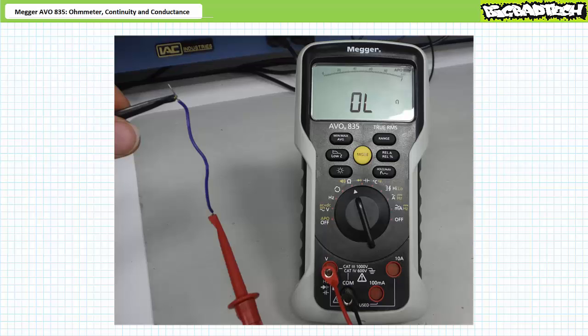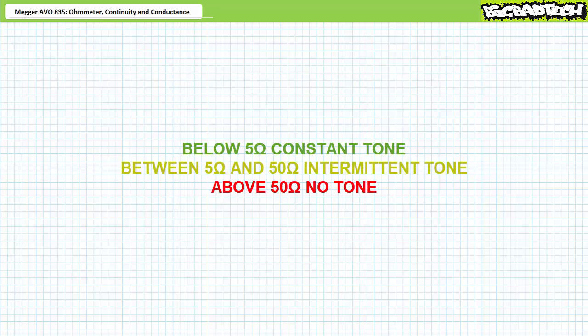Ohmmeter works for these types of checks. However, there's a better way to perform a continuity test. In addition to the numerical measurement of resistance, the AVO835 offers an audible continuity test. In summary, if there's a connection, it beeps. If there's no connection, it doesn't beep. On a more sophisticated level, the AVO835 emits a constant tone if the connection is below 5 ohms and an intermittent tone for connections between 5 and 50 ohms and no tone for connections above 50 ohms.